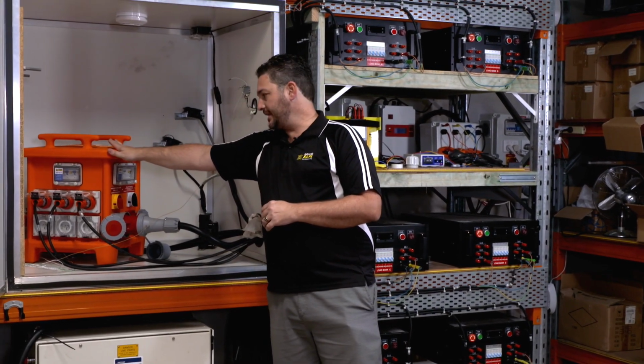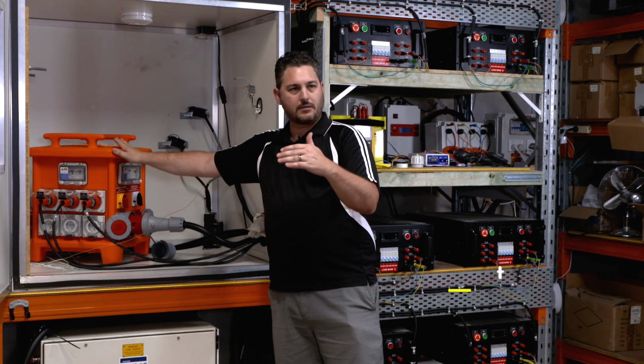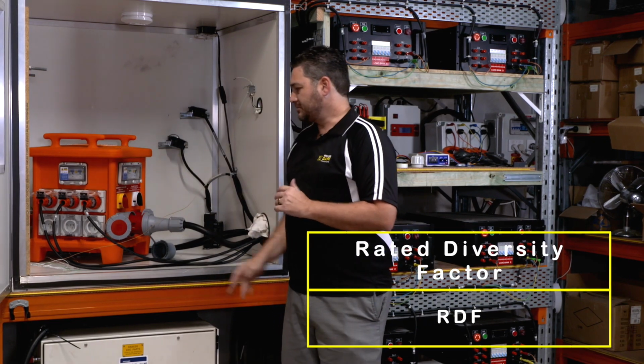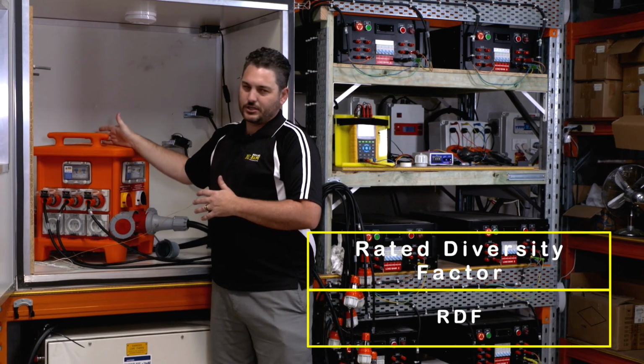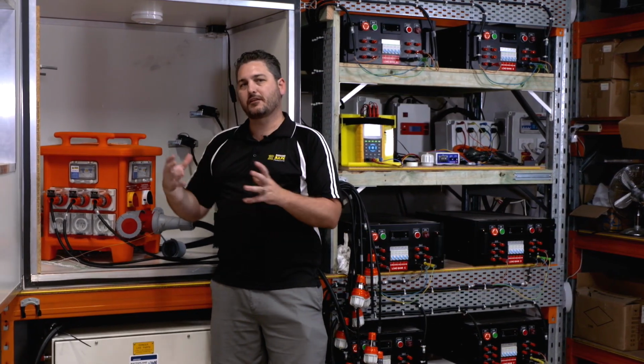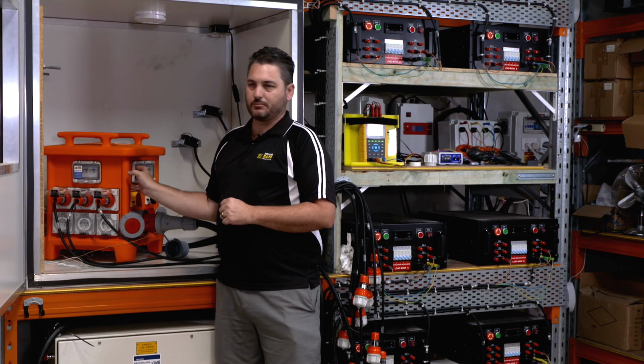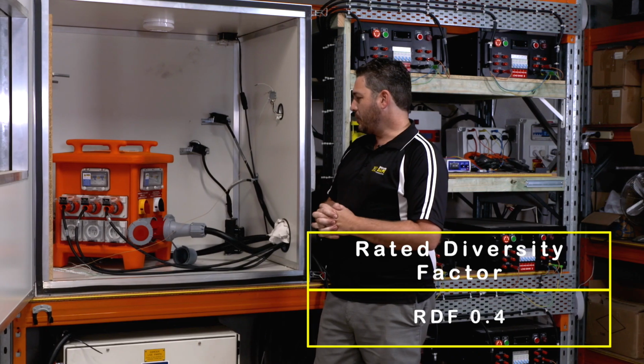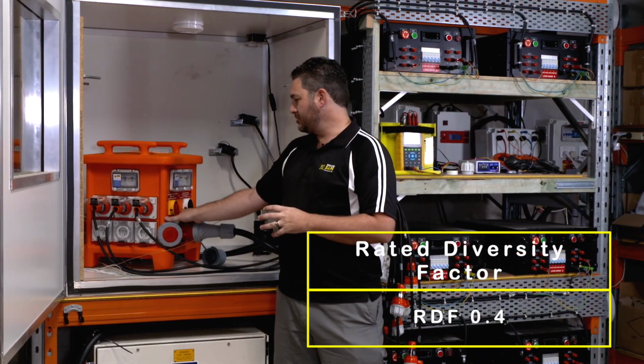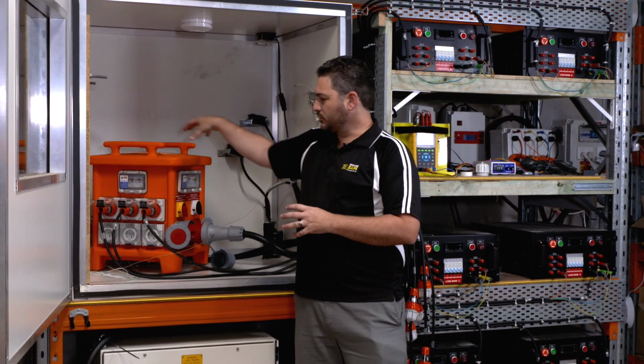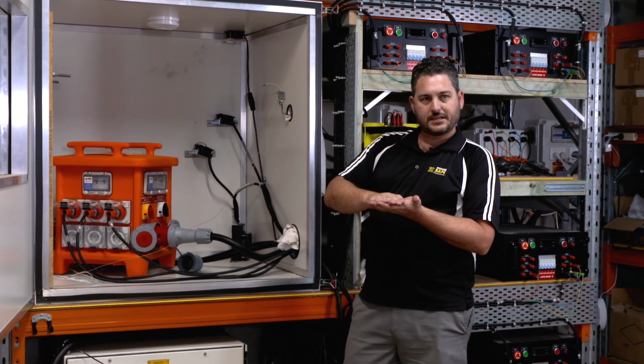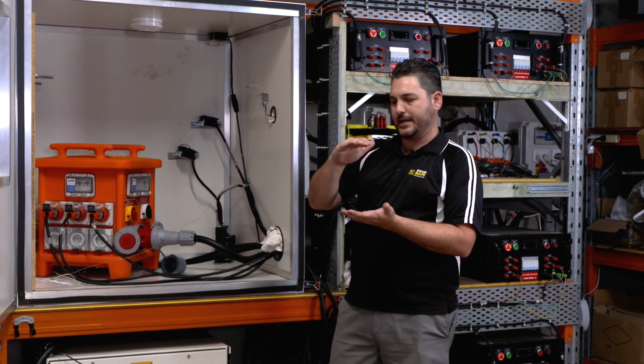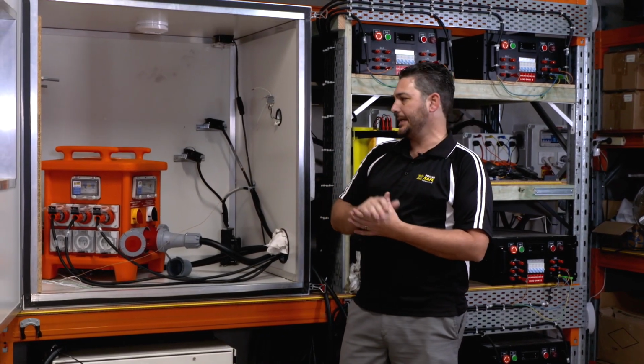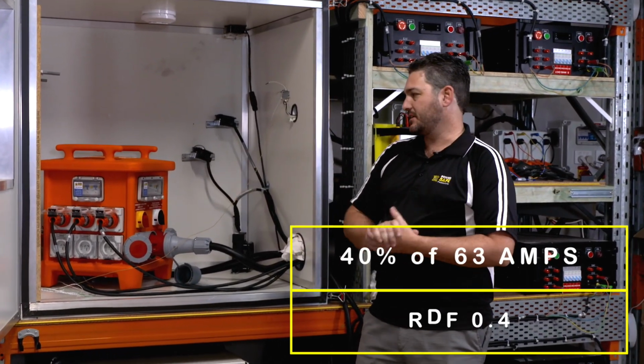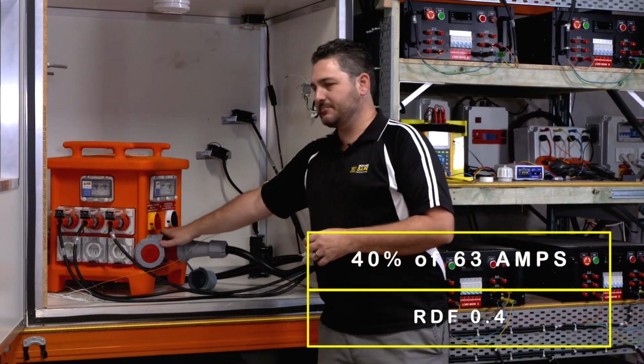The componentry will overheat. So what we do is we've got to come to our rated diversity factor, which is basically just a rating on the board to say, okay, you can pull X amount of power out without overheating the componentry. So for this board here, it's an RDF factor of 0.4. And the way we get to that is we run the power in through the board, we load up all the individual circuits, and we find what percentage of the total load can the board take without any of those components overheating. And for this board, it's 40%. So it's 40% of that 63 amps can be used.